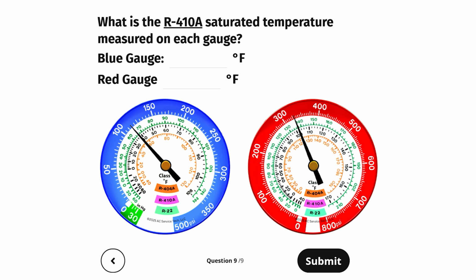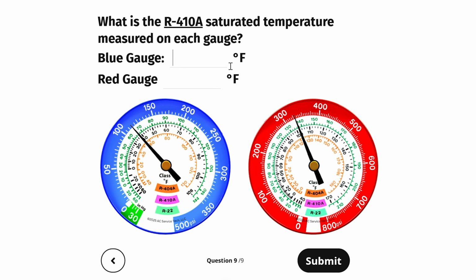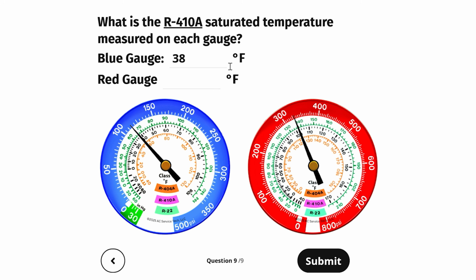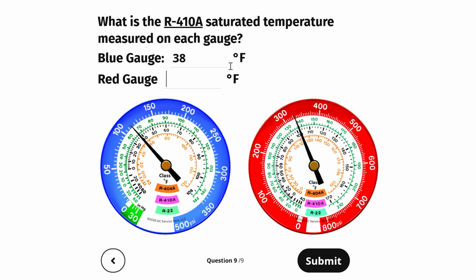What is the R410A saturated temperature measured on each gauge? And so for the blue gauge, we take the outer ring and we bring it in on the needle to the inner ring for R410A saturated temperature. It's in 2-degree increments, and so we measure 38 degrees Fahrenheit. For that red gauge, we take that dial, we bring it into the inner ring for the R410A saturated temperature, which is in 2-degree increments, and we measure 102 degrees Fahrenheit.